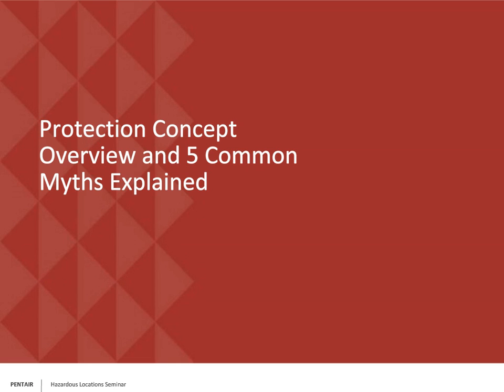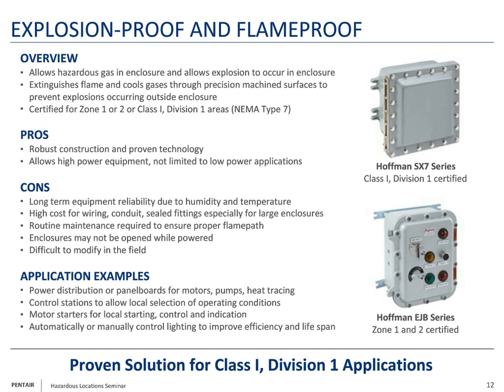So here's the most commonly used protection concept in hazardous areas: explosion-proof and flame-proof enclosures. They're applicable in Zone 1, 2, or Class 1 Division 1 areas, also known as a NEMA Type 7 enclosure. Again, a very heavy-duty enclosure designed to allow hazardous gases to enter the enclosure, and if there's arcing and sparking equipment, it creates a dangerous situation. That explosion can occur, but the enclosure is strong enough to withstand the explosion, and also has highly machined surfaces to cool the gases as they leave the enclosure.